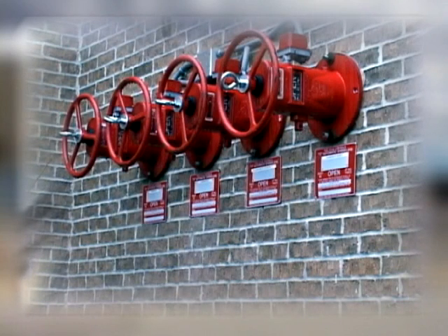Outside stem and yoke valves, located outside the building on the west and south sides, allow fire personnel to shut off the sprinkler system or AFFF foam system in a particular hazard room without taking the whole building out of service.